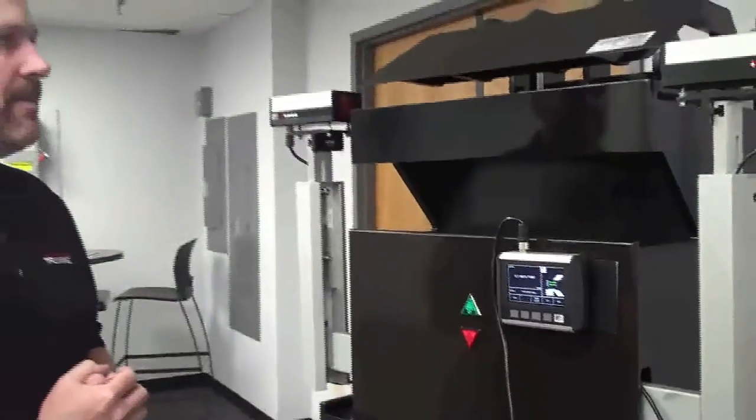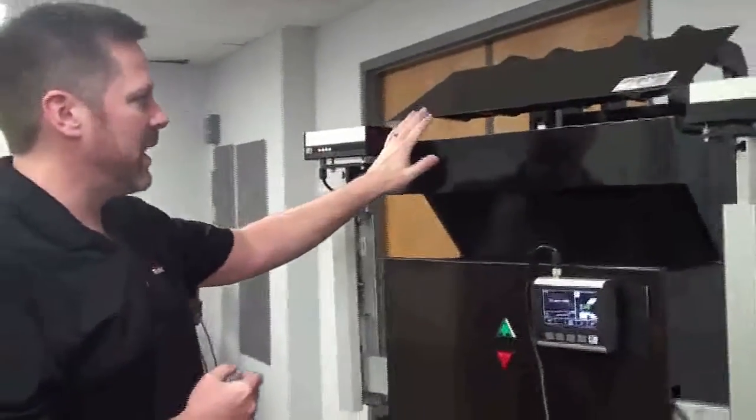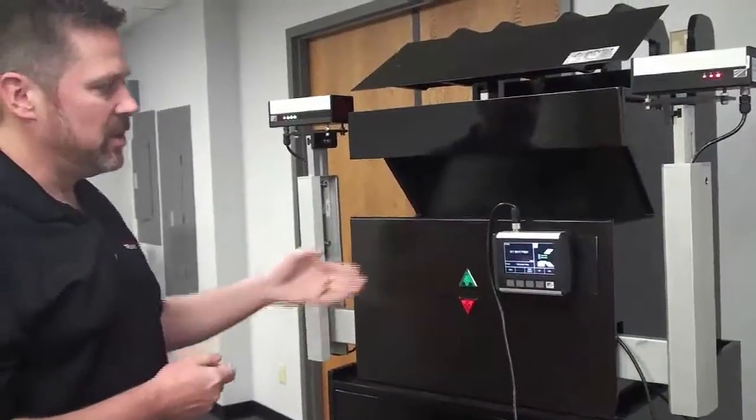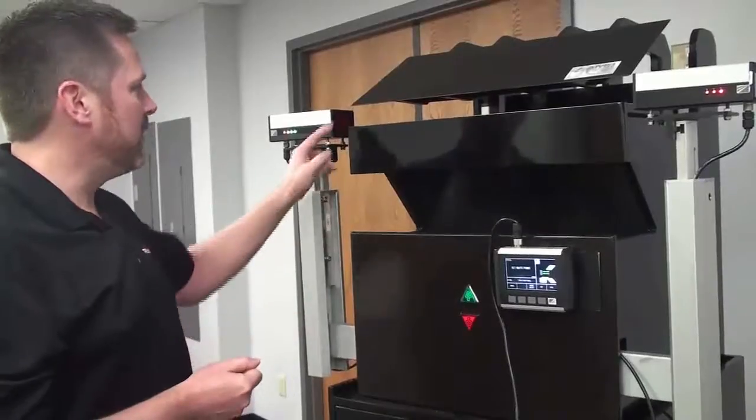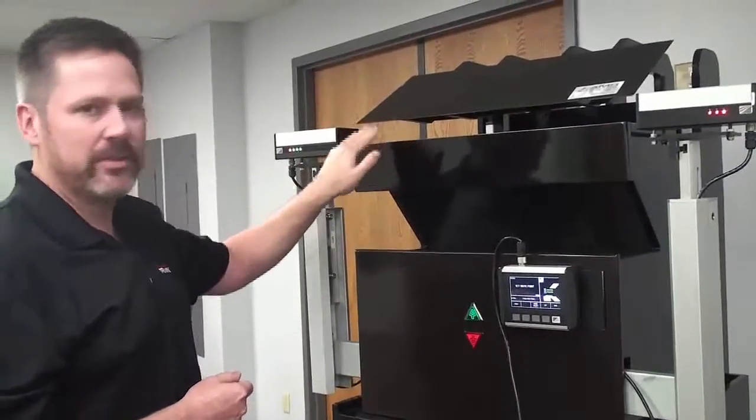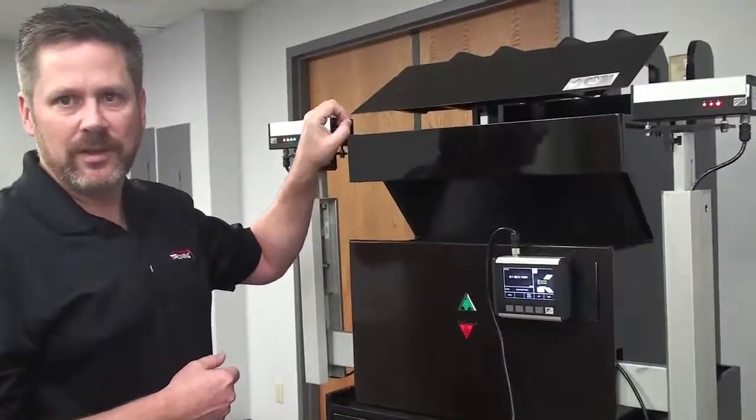What the mute point means is there are certain points in which this clamp is going to interrupt these lasers. The system uses the encoder to determine where these lasers are, so that way it can mute itself, so when the clamp passes through the lasers, it doesn't cause false stoppages.